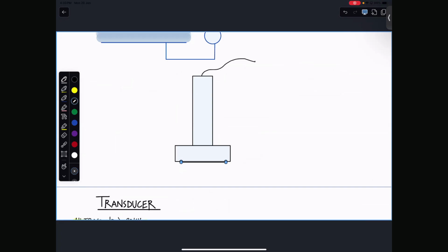Now here comes the important part. The piezoelectric crystal can't send and receive at the same time. It can send or receive. Do you understand why? Because when it's sending, there is a voltage across it. When it's receiving, there is a voltage generated by it. If you do both simultaneously, what will happen? They'll contradict each other, because it's a voltage you're providing and a voltage it's providing. They go in opposite directions, so it cancels out.